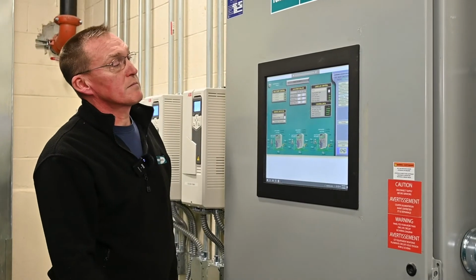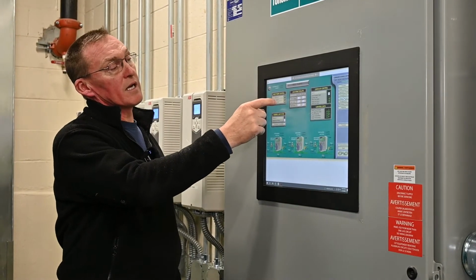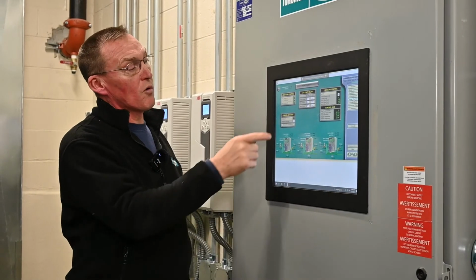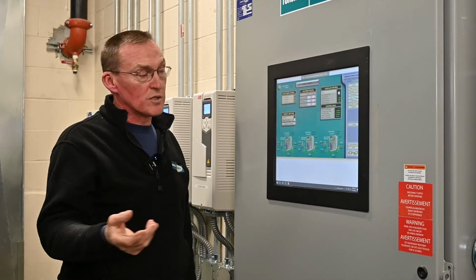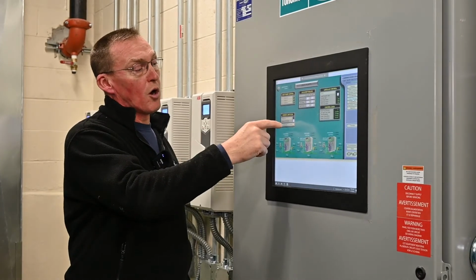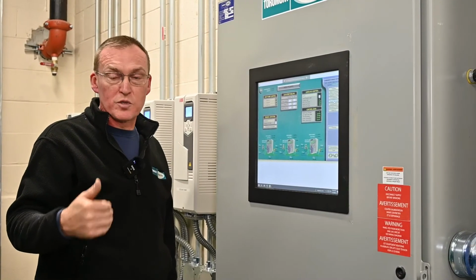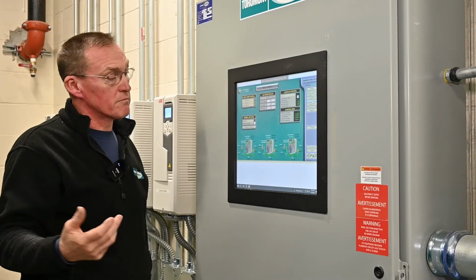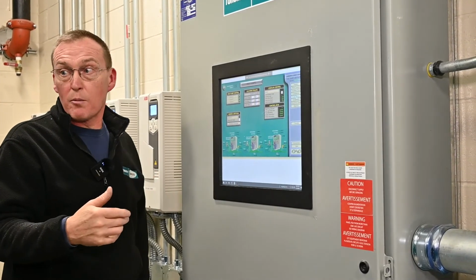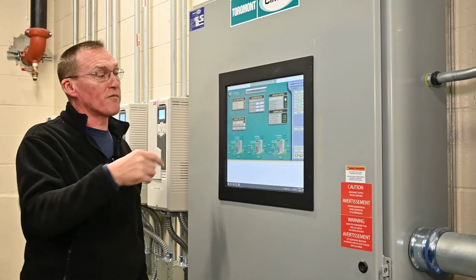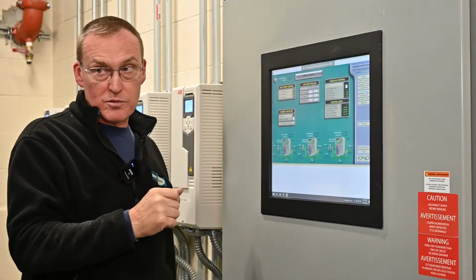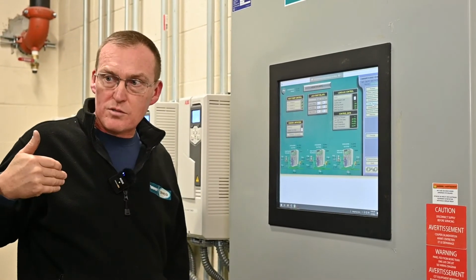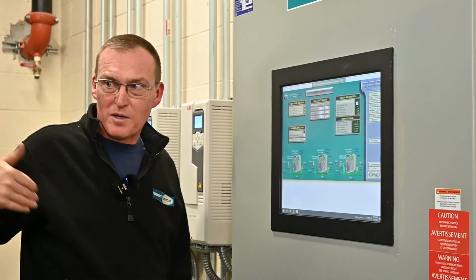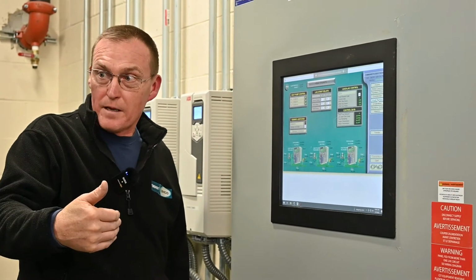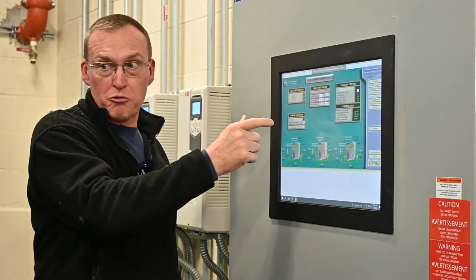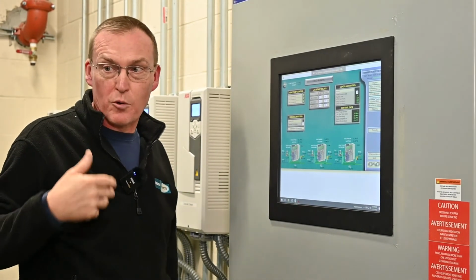Heat pump screen. You can enable or disable any of the heat pumps here. Again, I will go over demand limitation. If you want to save some energy, you can take one of those compressors off, set a schedule, say, hey, I only want to run 2 machines. You can go ahead and run 2 machines. It's fine. You'll have more than enough tonnage to do that with. Even if you enable your demand schedule, it will still cycle the compressors. So it'll go 1, 2, 3, then 2, 3, 1, and then 3, 1, 2. So even though you've got this demanded down to 2, you're still going to cycle each of the units. So you always have one in backup.